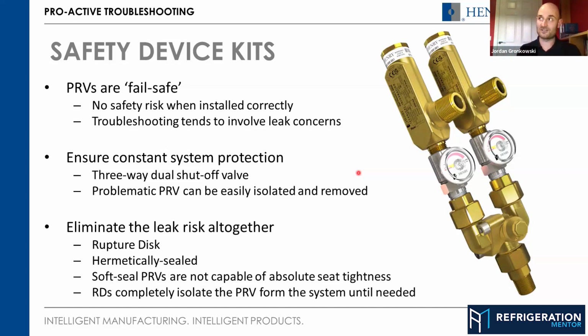You get manufacturers that use pop as set, like the valve will be set when it pops. You get manufacturers that use first audible, which I find astonishing, that the first time you hear the valve is when it's set. So you actually have to be listening to the valve, and if that thing goes off, you've got a burst eardrum. But this is what some people use as the definition. Yep. So anyway, it has to be set within that plus or minus 3%. Whatever your definition of set point, it has to happen within that plus or minus 3%.